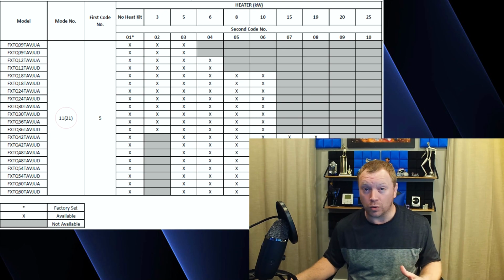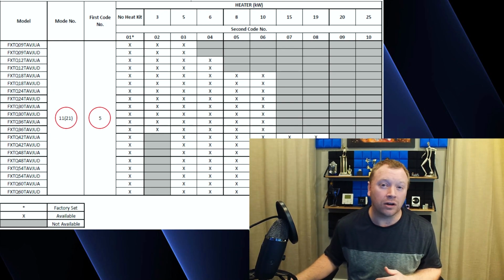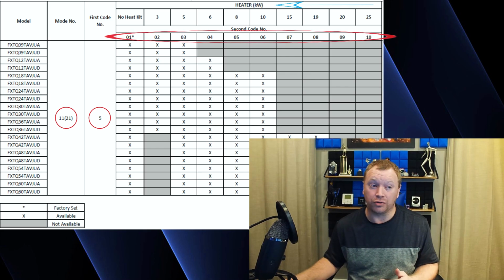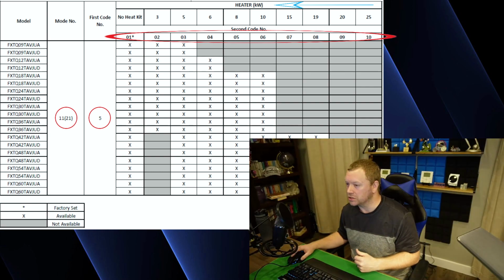Now, when you guys are installing the strip heater with the FXTQ air handler, it is important to make sure to record what size the air handler and what size the strip heater are, because there is a combination chart in the installation instructions for the FXTQ air handler. You can't just put any sized strip heater on any sized air handler. There is a combination chart, and that's actually the first setting you have to program into the controller for that indoor unit. You have to tell it what size strip heater you've installed. So what you're going to do is you're going to go into the field settings, you're going to go to mode 21, and then you're going to go to setting 5, and depending on the size of the strip heater, you're going to change it from 5-01, which is the default. That means you have no strip heat kit installed, to either 5-03, 5-04, 5, 6, 7, 8, 9, 10, whatever size strip heater that you have.